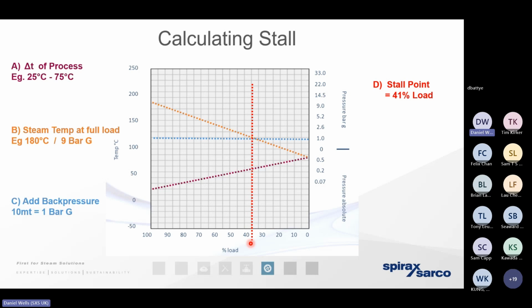That's not going to mean a great deal to most engineers. But if we can calculate the point at which the stall point intersects the process line, then we can convert that to a temperature. So when the return temperature on the secondary side increases to 52 degrees, the demand for steam falls to a point where we no longer have enough motive energy to move the condensate across the trap. So when the process condition exists within that yellow triangle, we know for a fact that the condensate is going to back up and result in a number of inefficiencies and problems with the process. The question is, what do we do about it?